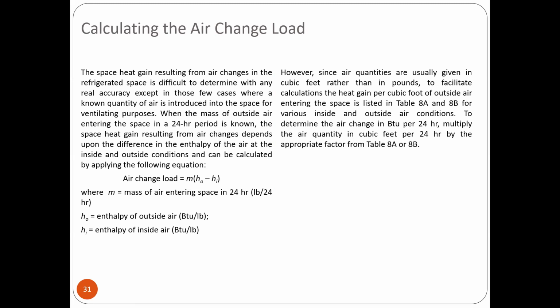Air change load is equal to M times (h_o minus h_i), where M is the mass of air entering the space in 24 hours, h_o is enthalpy of outside air, BTU per pound, and h_i is enthalpy of inside air, BTU per pound. However, since air quantities are usually given in cubic feet rather than in pounds, to facilitate calculation, the heat gain per cubic foot of outside air entering the space is listed in tables 8A and 8B for various inside and outside air conditions. To determine the air change load in BTU per 24 hours, multiply the air quantity in cubic feet per 24 hours by the appropriate factor from tables 8A and 8B.